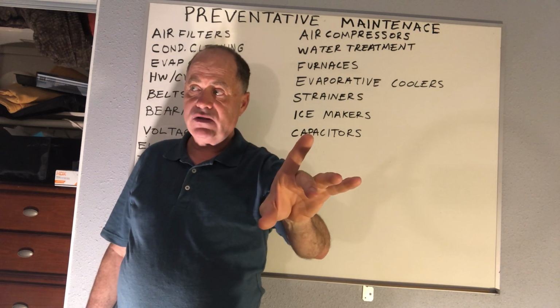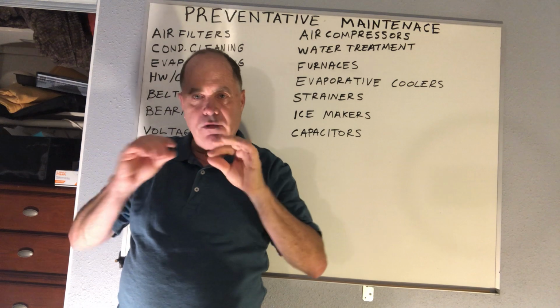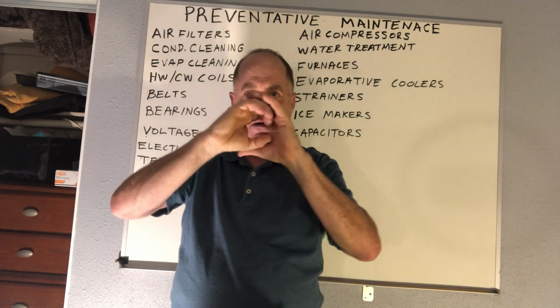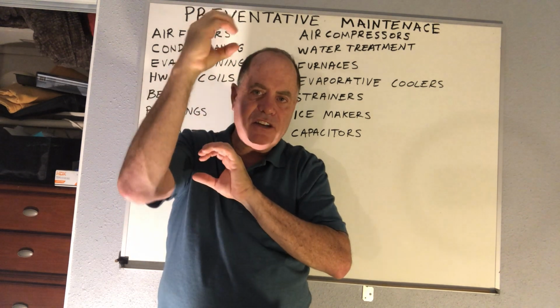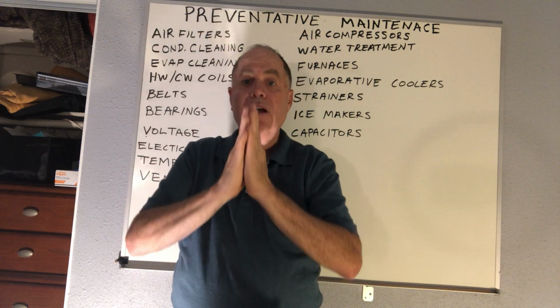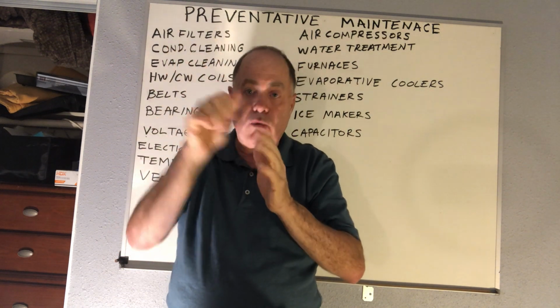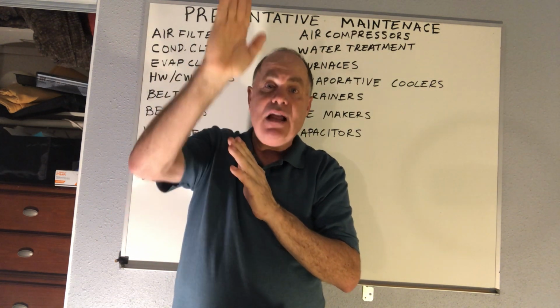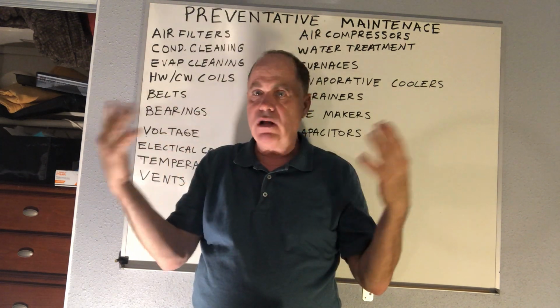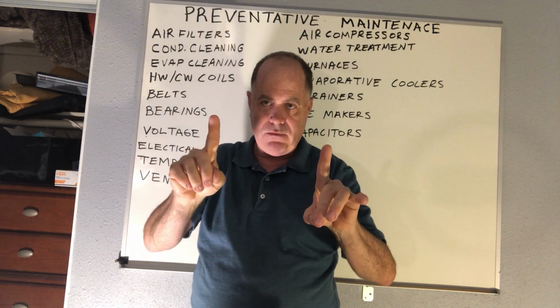through those coils, is the air in the water, the tiny bubbles in the fill water. They find their way to the top and plug up the very highest coils with air, and then you don't get good flow. So you should have an air vent that's letting the air off the top. But if that's not working, you have to manually open a valve and let the air off the top, and then it will work. Those are some good tips for when you're like, I don't understand, I don't get it. Do that.